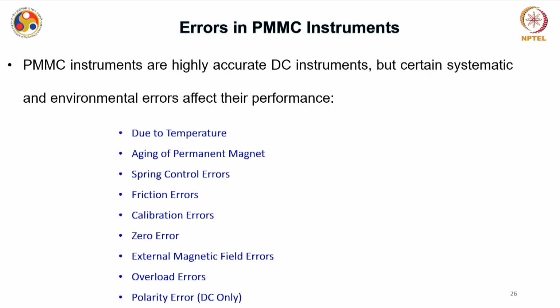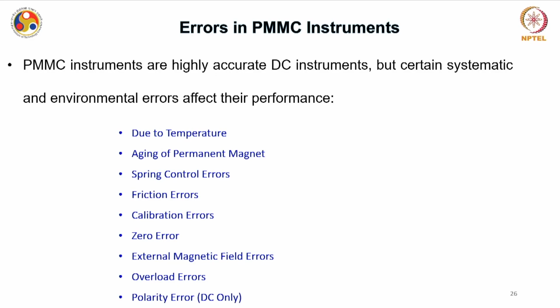There are also calibration errors, zero errors, and errors due to external factors like external magnetic fields. Then there are overload errors, since these instruments are polarity based, meaning you have to connect positive to positive or negative to negative. There can be some man-made or human errors like polarity errors, which is very sensitive for a DC instrument. If you have the wrong connection, you may not get the correct reading.